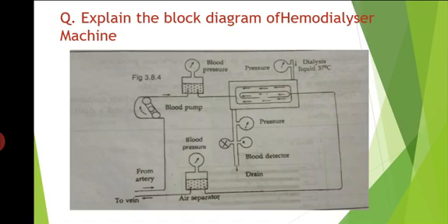In this, a number of membranes are pressed together, and alternately the dialysis solution flows. In the opposite direction, blood flows. Whenever more waste products are present in the blood, the concentration gradient is higher in the blood, so the waste products are absorbed into the electrolyte solution.